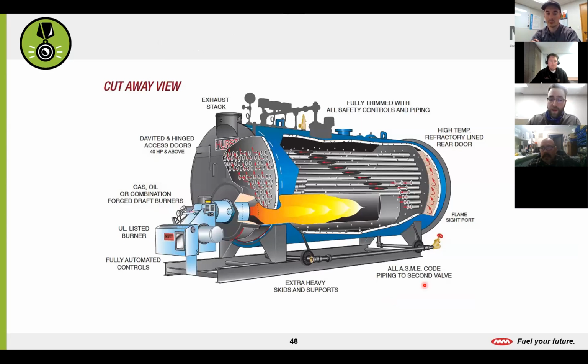All right, and then we have a fire tube boiler, non-condensing fire tube boiler. This is the big one here. So if we look here, and this is just a general example of the operation of one and how it works, we have this guy here. This is our burner assembly. So this is what gives us the heat. We'll have gas feeding into this guy, and then we'll have some kind of ignition source, whether that's a spark generator or hot surface igniter, something that glows hot and ignites that gas, something to give us the flame, right? And it'll shoot our flame into our main barrel burner here.